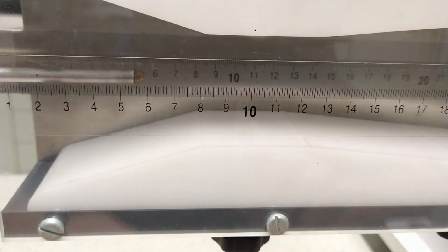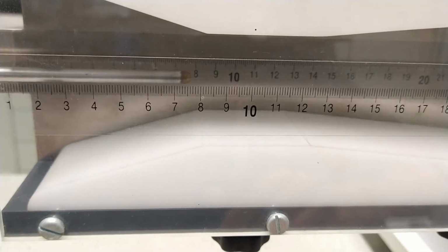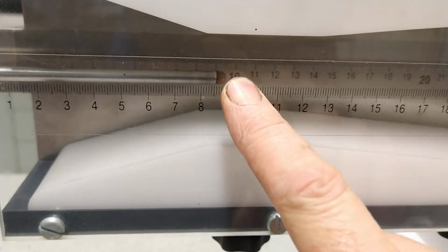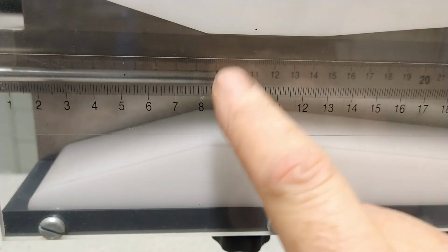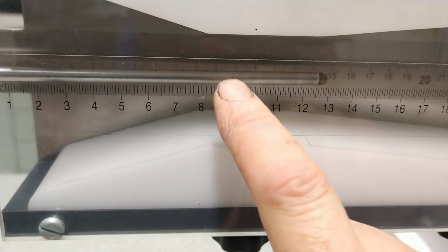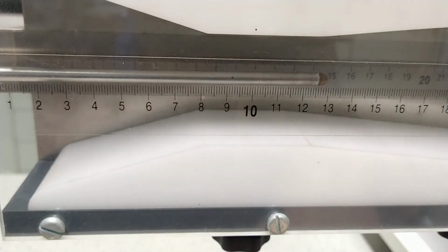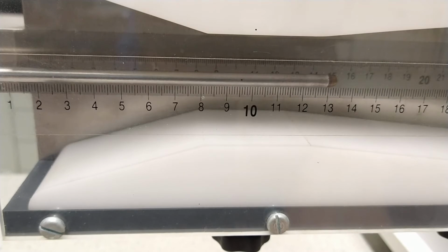So what you can use that for: the pitot pressure at the front measures both the static pressure and velocity pressure, and the ports at the side only measure the static pressure. If you take one away from the other, that allows you to work out the velocity pressure at different locations along the system. You can measure the velocity pressure and the static pressure at different locations, and that'll allow you to plot out graphs of the pressure distribution and also the velocity profile at different points in the system.